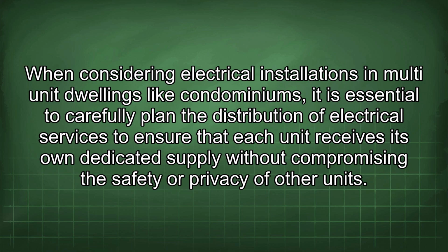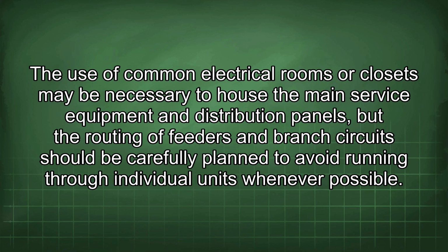When considering electrical installations in multi-unit dwellings like condominiums, it is essential to carefully plan the distribution of electrical services to ensure that each unit receives its own dedicated supply without compromising the safety or privacy of other units. The use of common electrical rooms or closets may be necessary to house the main service equipment and distribution panels, but the routing of feeders and branch circuits should be carefully planned to avoid running through individual units whenever possible.